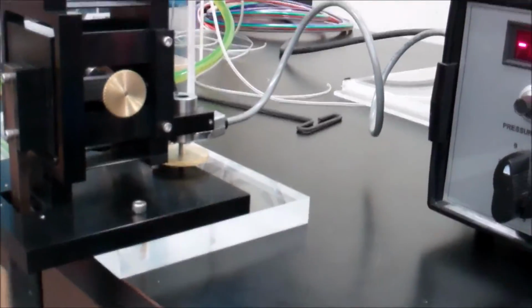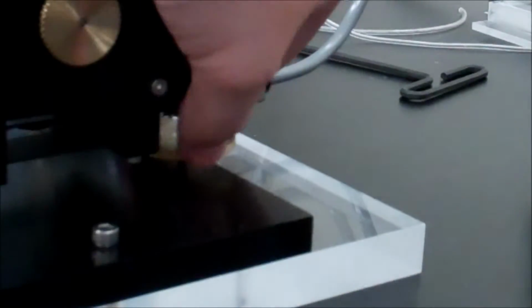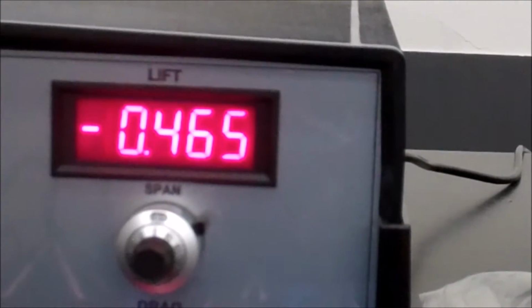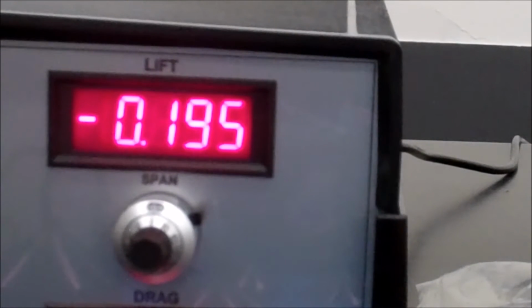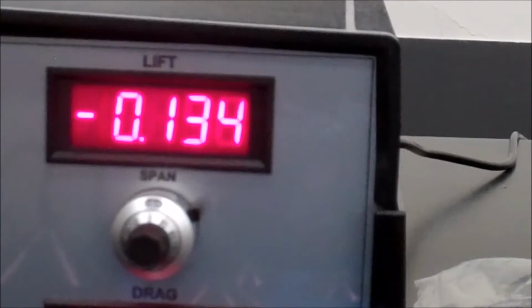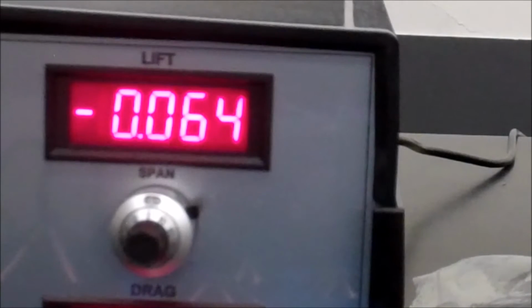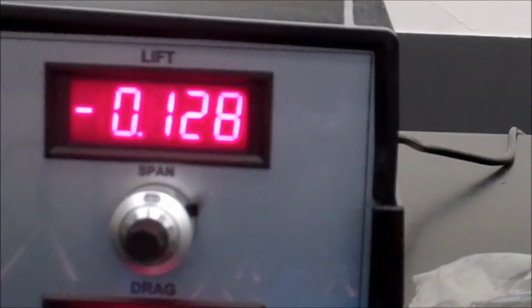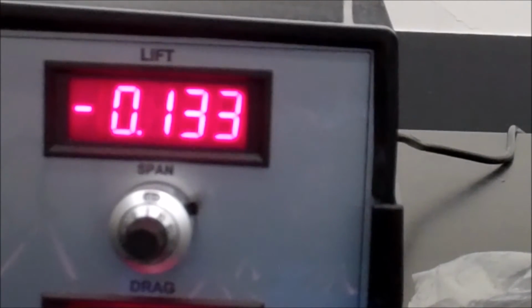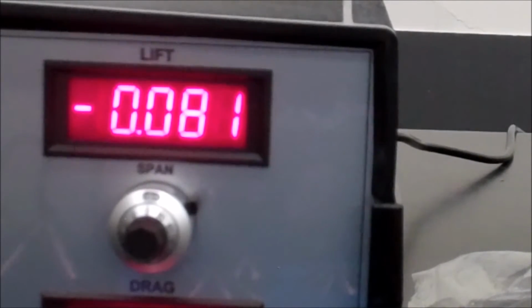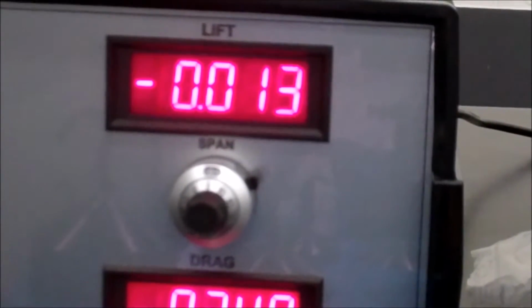You can zero the voltage output of the system before you calibrate it by using this knob right here. If I look at the digital manometer part, I'll start turning the wheel, and you notice it turns in a certain direction, and I get it as close as I can to 0. These are very touchy, so if you don't get it exactly at 0, that's okay, but you can at least change the offset close to 0. You can see it's very touchy, so then you can zero it out before you start your calibration. And that's how you calibrate for lift.